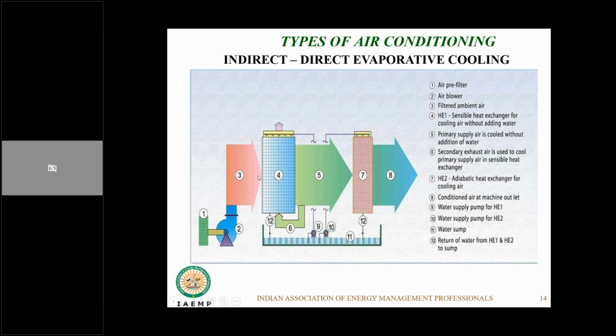So let's take an example over here. Let's say we have a 40-degree air coming in from here, which has to go further into our room for conditioning, and we have an exhaust air stream coming in at 40 degrees centigrade. This exhaust air in the indirect heat exchanger is cooled to almost its dew point, say around 25 degrees centigrade, which would be a wet bulb temperature in a current scenario. This 25 degree air, cooled to saturation temperature, is used to cool this 40 degree air coming in. Normally, the efficiency of this heat exchanger is around 60%. So we have a temperature difference of around 40 to 25, so almost around 15 degrees centigrade. So you have almost around a 9-degree drop in temperature, and so the 40 degree air coming out of the heat exchanger would be around 30 degrees centigrade.